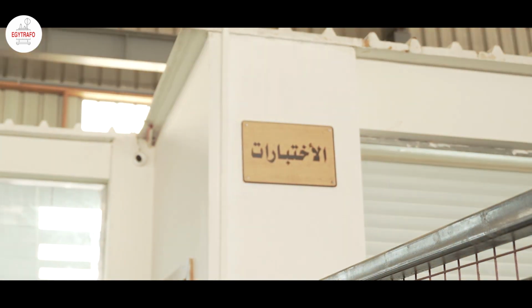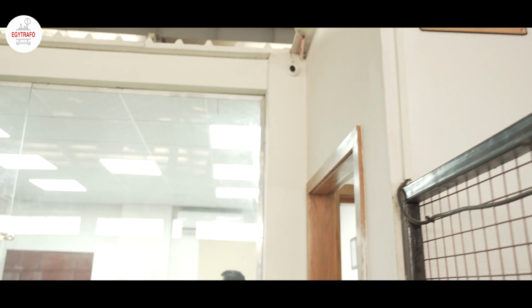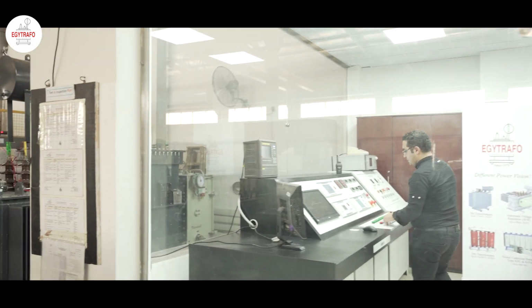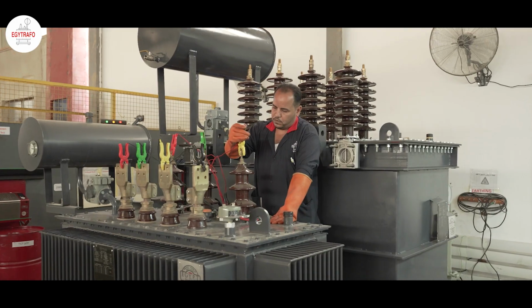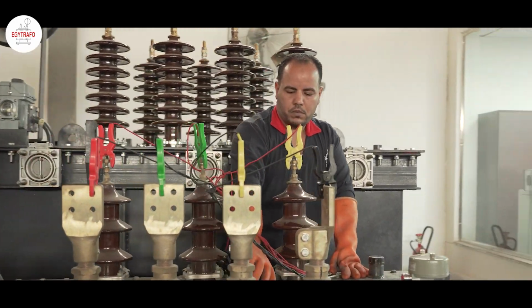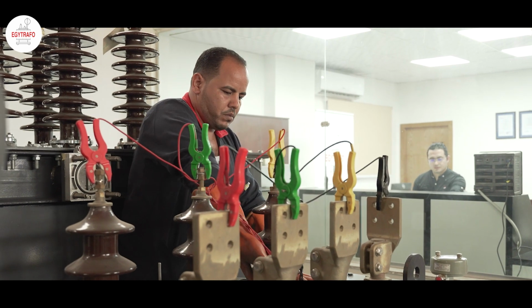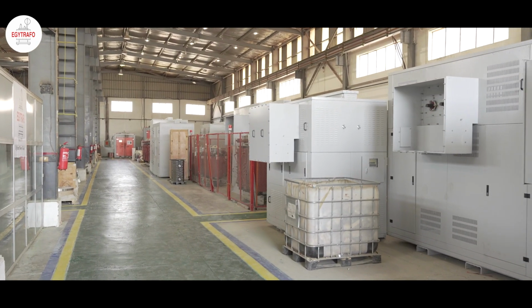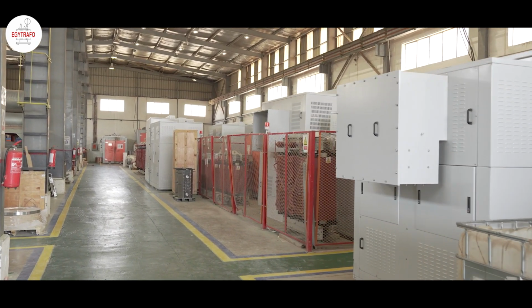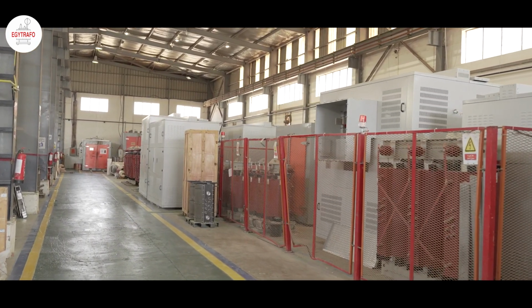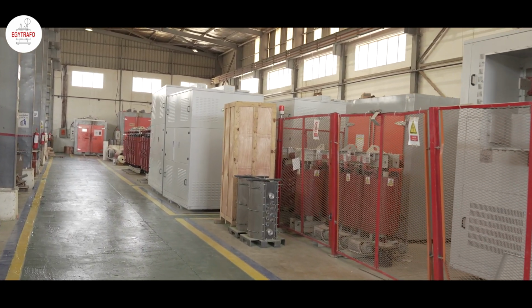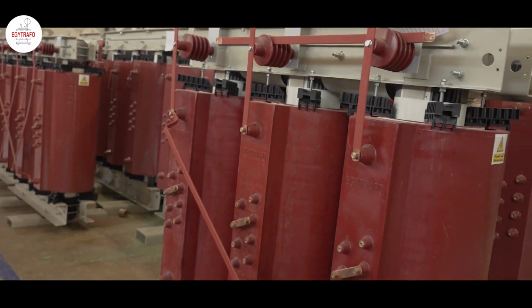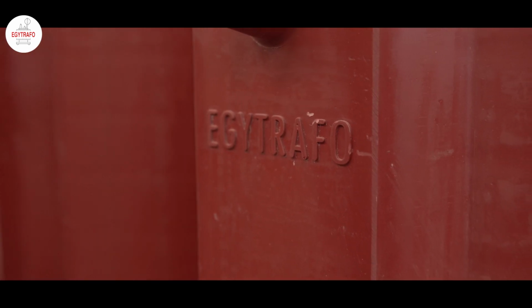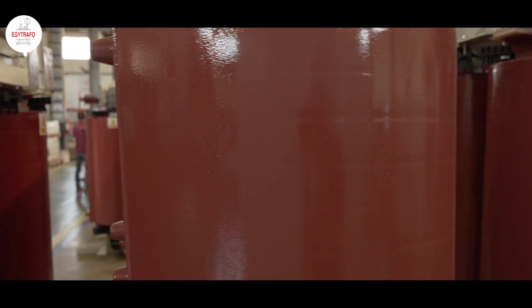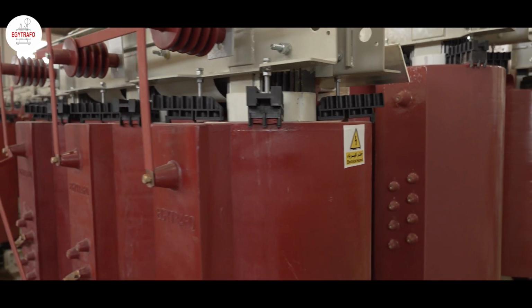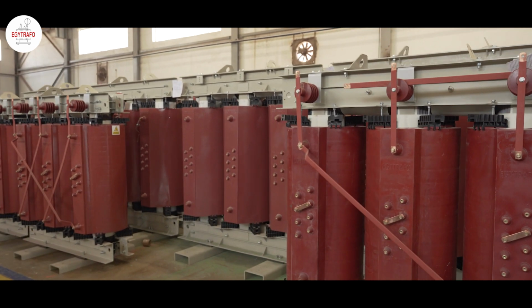At the end of the manufacturing process, the transformers are individually tested in accordance with the IEC standards. The routine tests are according to IEC 60076-1. Upon request, witness type or special tests can be carried out. As a result of Egytrafo's obviously achieved success in transformers manufacturing, according to the latest IEC standards, by means of the latest production technology and highest quality standards, in addition to meeting customers' requirements, which encouraged us to step further in our dream, in which we established the first dry transformers factory in Egypt in 2007.